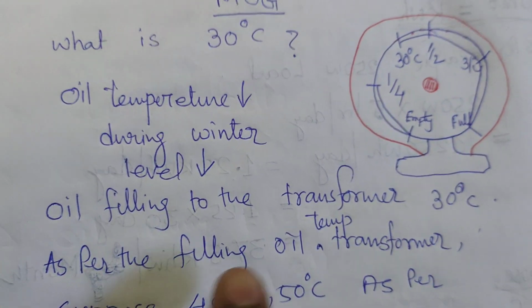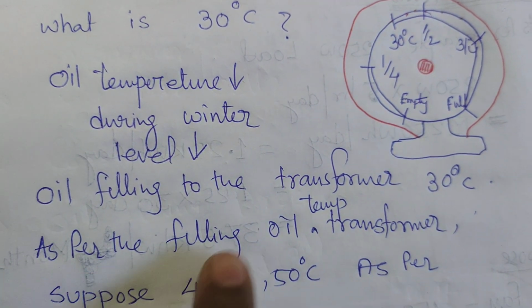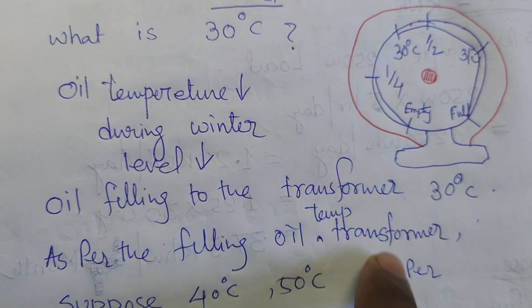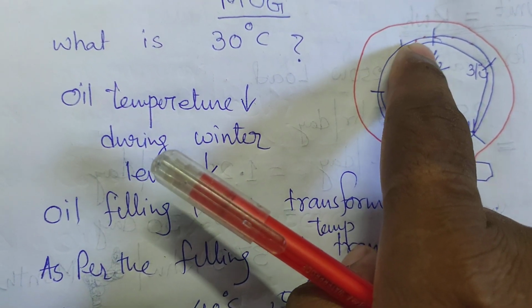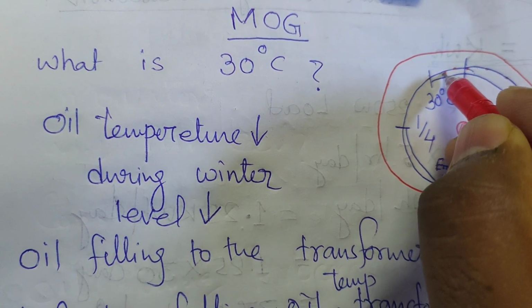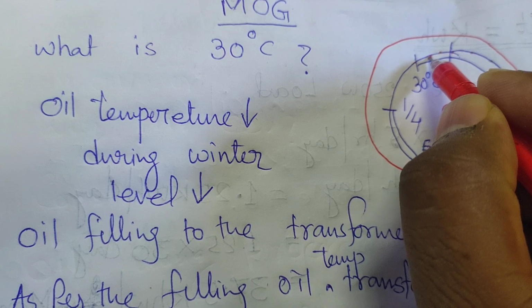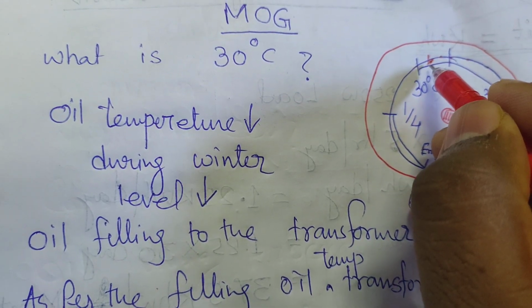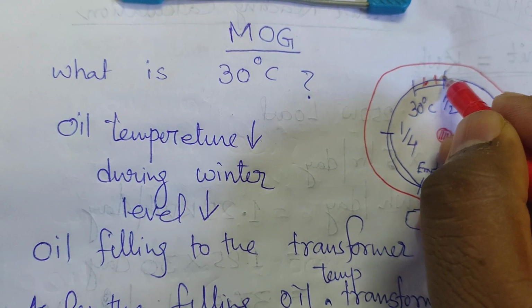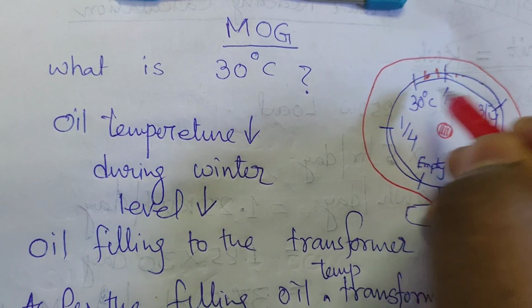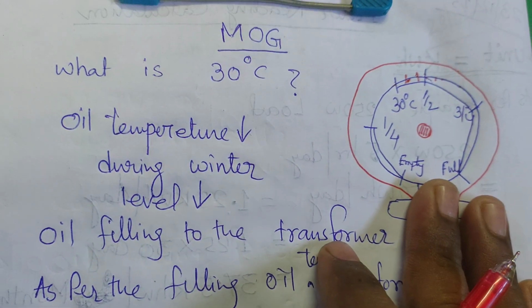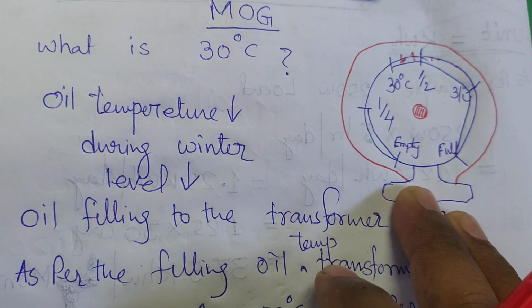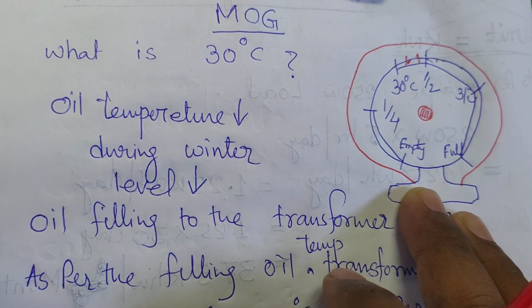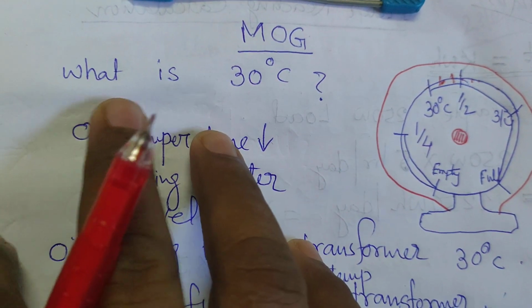So if the oil filling of the transformer is up to 30 degrees Celsius, then the oil temperature inside the transformer's conservator is 30 degrees. Suppose it is 40 degrees, 50 degrees, as per the temperature, if it is increasing, 30 to 40, 40 to 50. If you are maintaining a 40 degree temperature inside the transformer as per the load calculation and the present load, you have to fill the oil up to this point. This is 40 degrees, this is 50 degrees, this is 60 degrees, this is 70 degrees. As per your requirements, the present scenario, the present position of the transformer and the loadability of the transformer, you can choose the oil level inside the conservator. So you clearly understand why 30 degrees Celsius is put here.